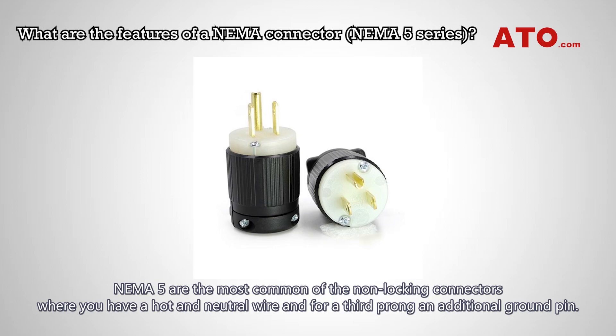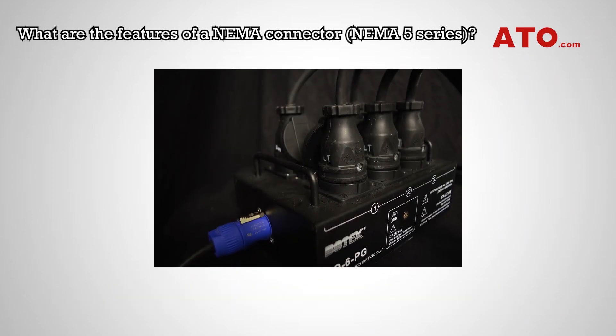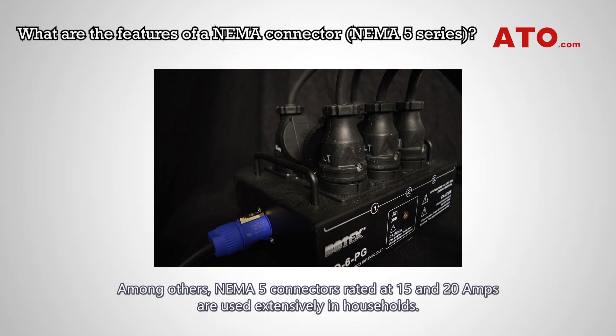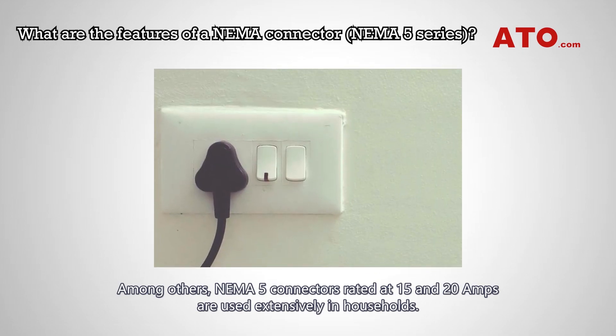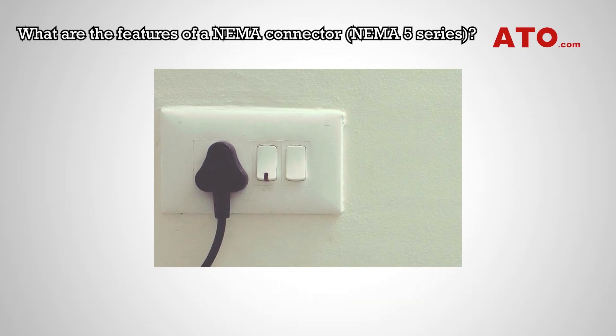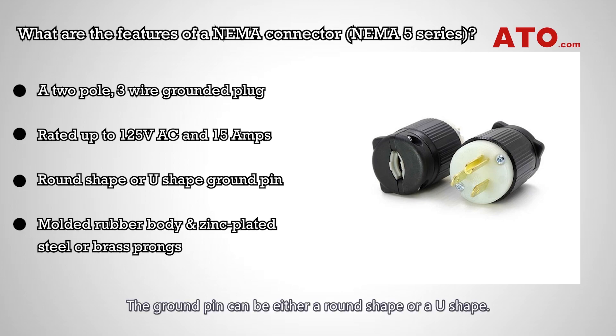NEMA 5 series is the most common non-locking connector, where you have a hot and neutral wire and for a third prong and additional ground pin. Among others, NEMA 5 connectors rated at 15 and 20 amps are used extensively in households. The NEMA 5-15 plug is a 2-pole, 3-wire, grounded plug rated up to 125V AC and 15 amps. The ground pin can be either a round shape or a U-shape.